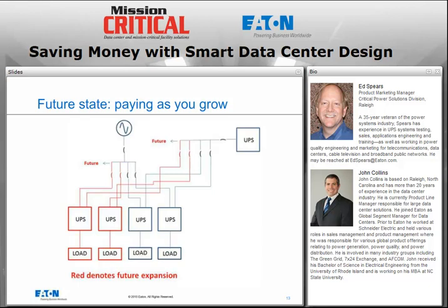Don't know how big it'll be, but it doesn't matter. I can choose the breaker size and install in my existing switchgear and choose the UPS size on an as-needed basis. And while we have this picture up on the screen, it's worth mentioning that the catcher UPS shown here in the far upper right could operate in a high efficiency mode like our energy saver system.